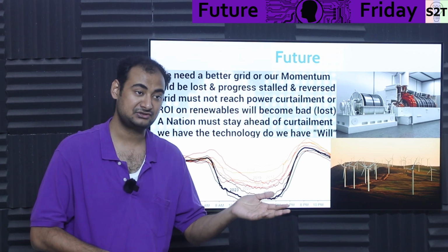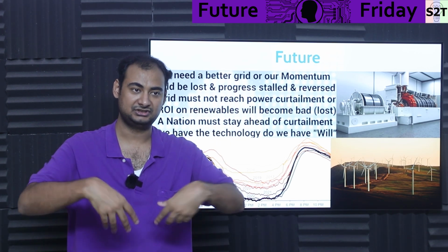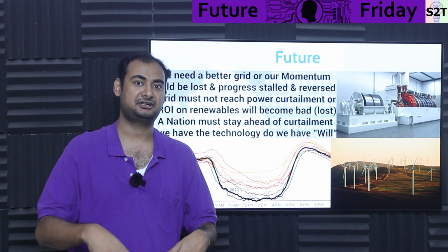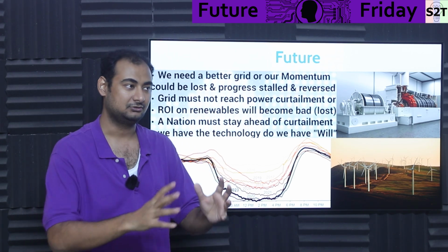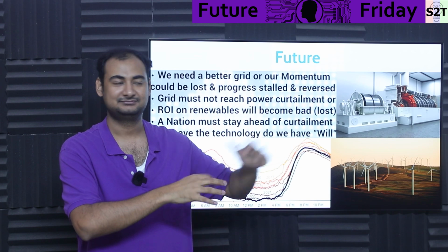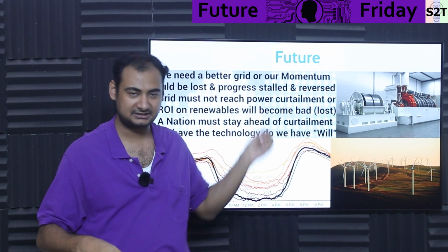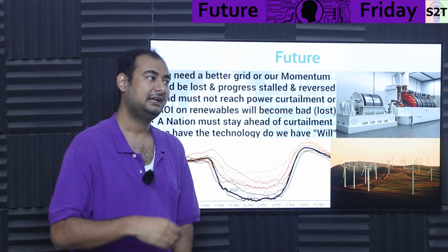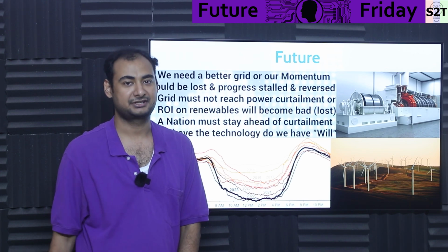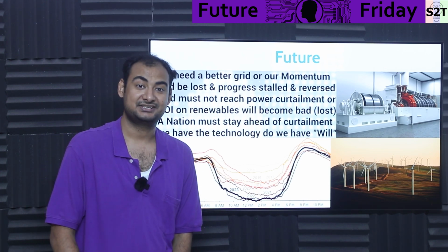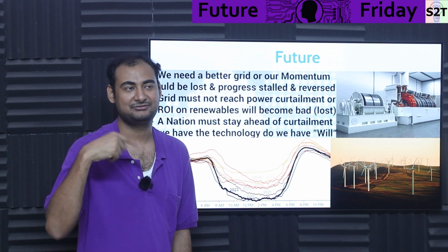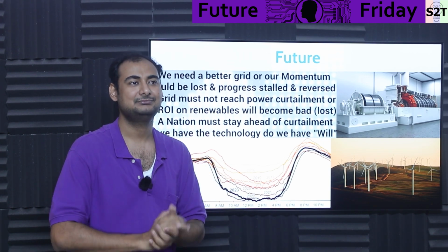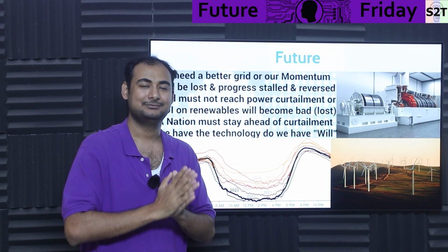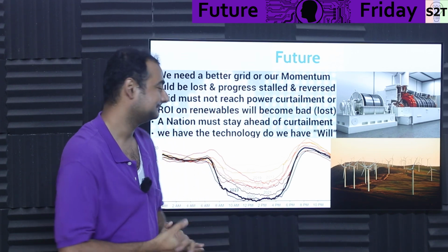And because of the development in solar, people looked at it and they took that gearbox, yeeted it, took that doubly fed induction generator, yeeted it, and just put a BLDC motor there. And now it's completely free, directly rotating, directly getting power out of it. And what about the frequency? Now there is an inverter there. Consequence: there is no inertia. Inertia was reduced the moment we had an electrically fed system, but it still had some oomph to it. Now it's gone. It's completely free floating.